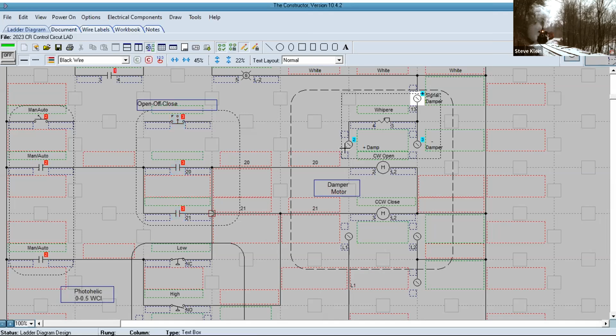So the next one I want to go on is a little bit further over here to the right-hand side, where we've got the wiper for the control motor out in the actuator on the damper motor. You've got an open motor and a closed motor out there that's trying to drive the damper clockwise and counterclockwise. Everything in that dashed area is actually connected to the actuator itself.